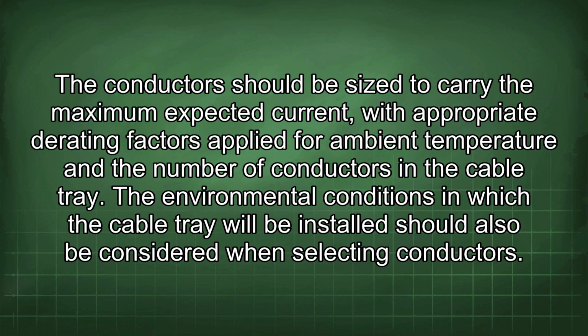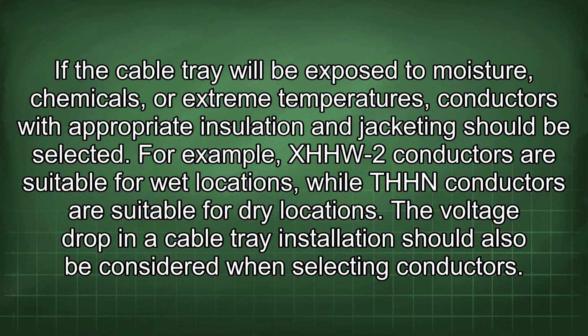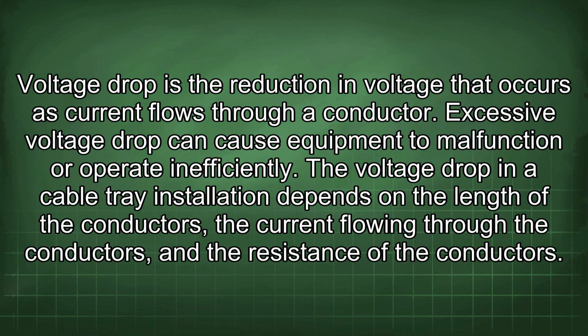The environmental conditions in which the cable tray will be installed should also be considered when selecting conductors. If the cable tray will be exposed to moisture, chemicals, or extreme temperatures, conductors with appropriate insulation and jacketing should be selected. For example, XHHW-2 conductors are suitable for wet locations, while THHN conductors are suitable for dry locations. The voltage drop in a cable tray installation should also be considered when selecting conductors. Voltage drop is the reduction in voltage that occurs as current flows through a conductor. Excessive voltage drop can cause equipment to malfunction or operate inefficiently.